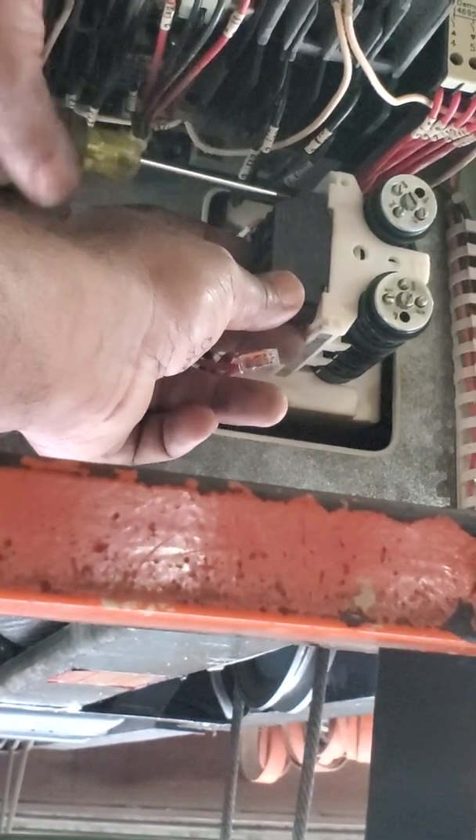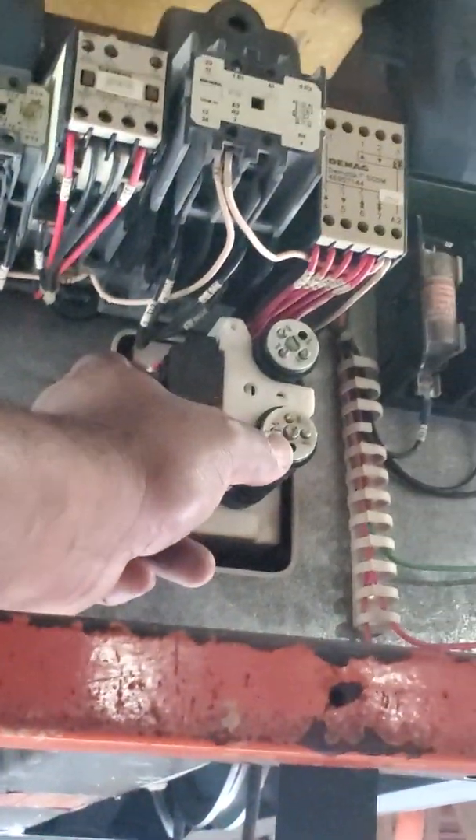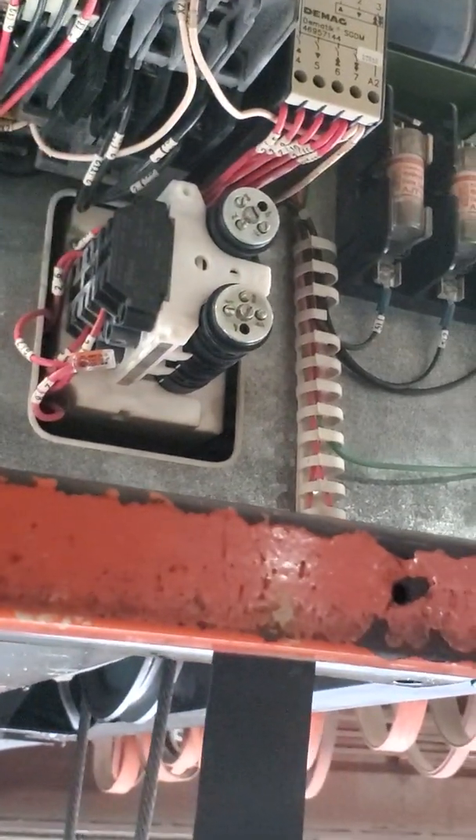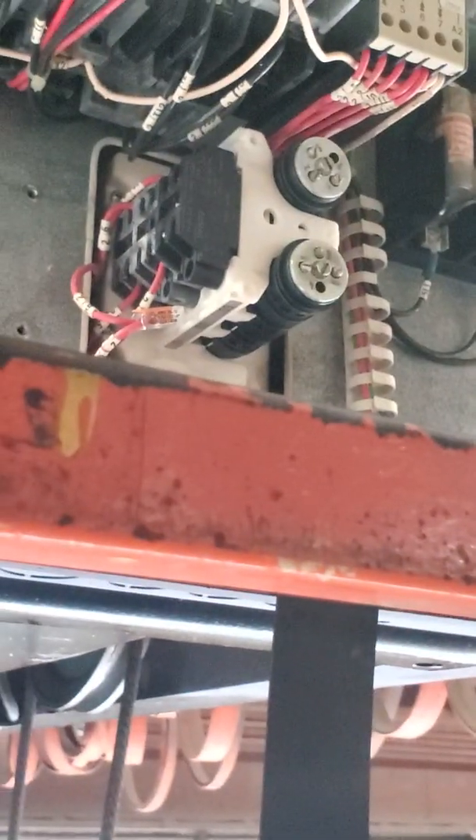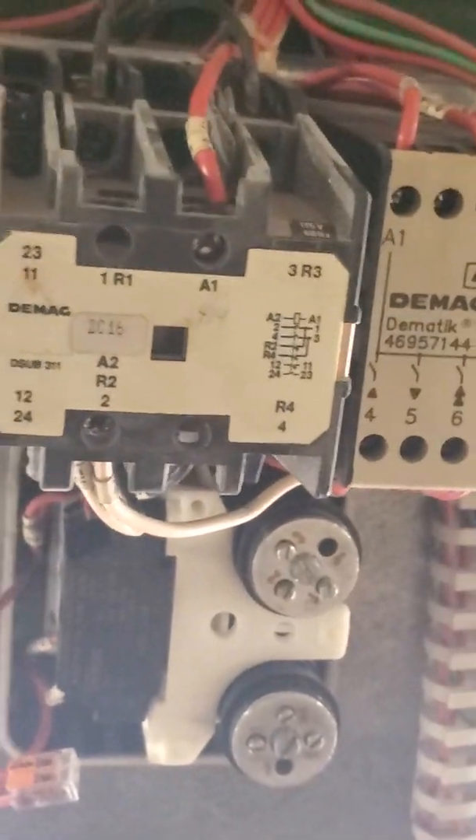You know the switch will not be any good if you break it or you break the housing. Now you can see there are fuses and reversing contactors there. This one is the high speed contact — this one for high speed up and high speed down. And there's a load limiter here, and a load contact here.